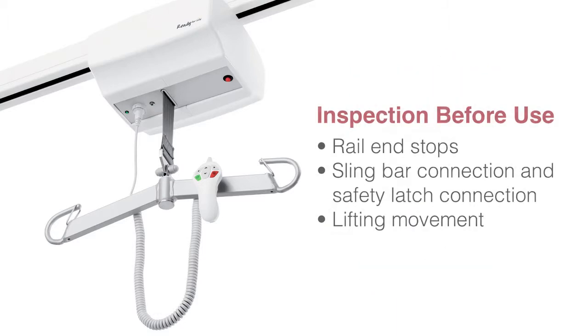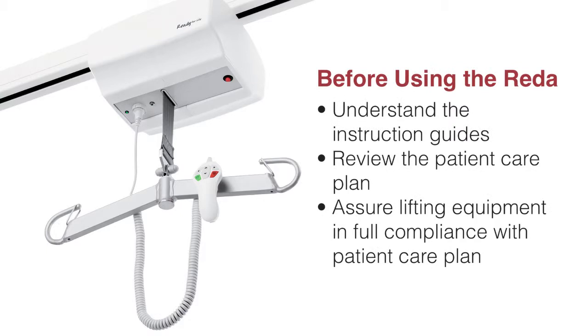Prior to using the lift, check rail end stops, check sling bar connection and safety latch connections, and check lifting movement. Before using the Reda, all operators should carefully study and understand the instruction guides for both the lift and accessories, as well as complete the Reda competency checklist. The patient care plan should always be reviewed for the patient's activity level and any contraindications for using a lifting device.